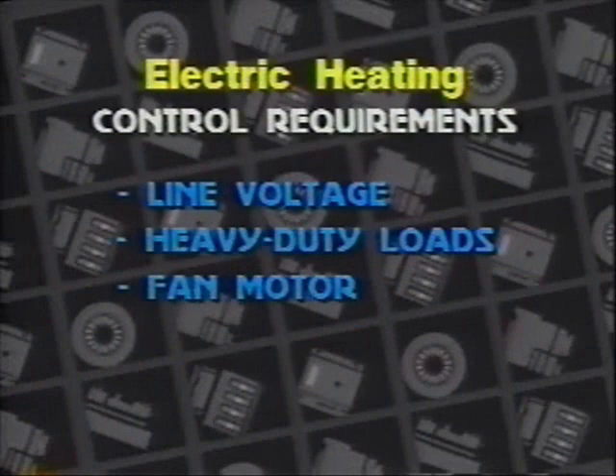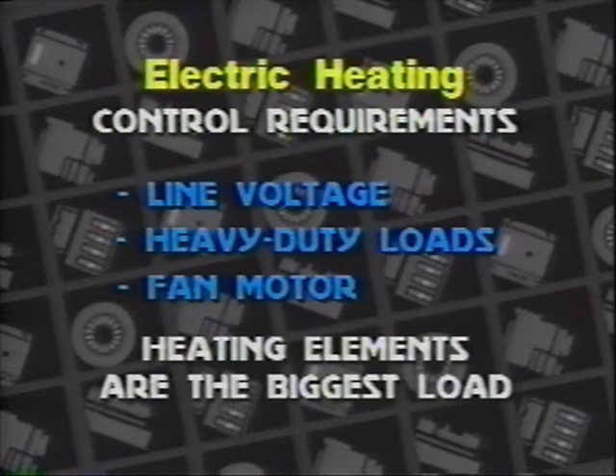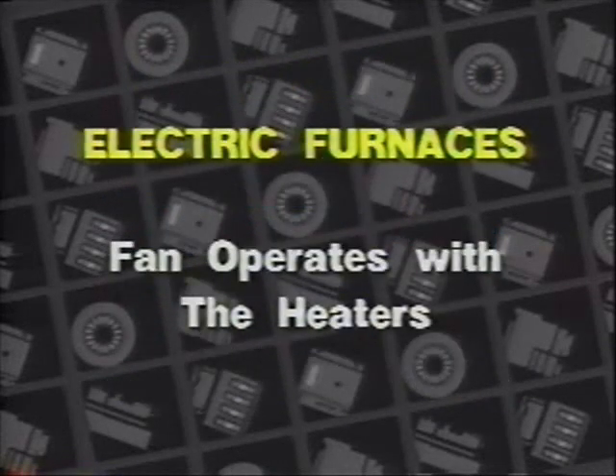The control requirements for electric heating are similar to those for air conditioning. Both require line voltage, heavy-duty load switching, and fan motor switching. In electric furnaces, heating elements account for the biggest load. One peculiarity of electric furnaces is that the fan must always come on at the same time as the heaters, because heat is produced almost instantaneously.